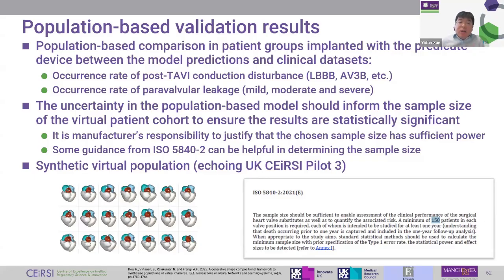And the manufacturer also needs to consider the uncertainty in their population-based model, which should inform the sample size they choose for their virtual patient cohort to ensure their results are statistically significant. We also highlight that it's the manufacturer's responsibility to justify that the chosen sample size has sufficient power in their analysis, but we can get some information on the order of magnitude of the in-silico patients we need from some existing standard. For example, from this ISO 5840-2, we can see that for each valve position, the manufacturers require at least 150 patients in their clinical trial, and they need to follow up for 1 year.